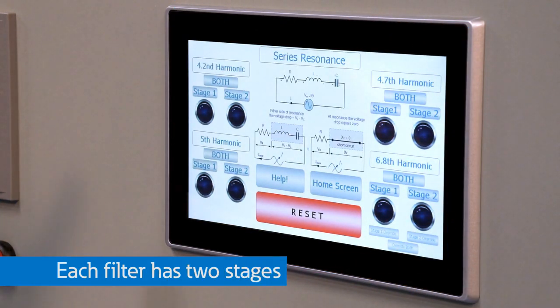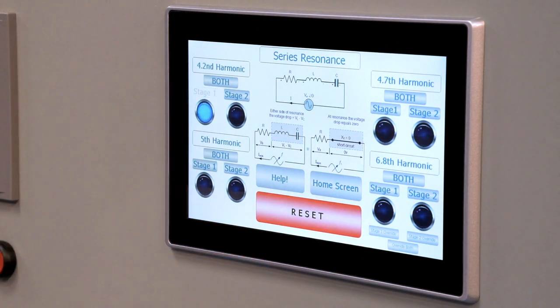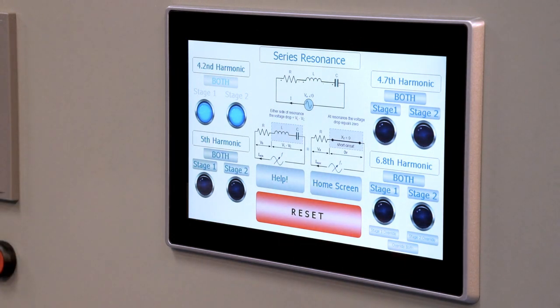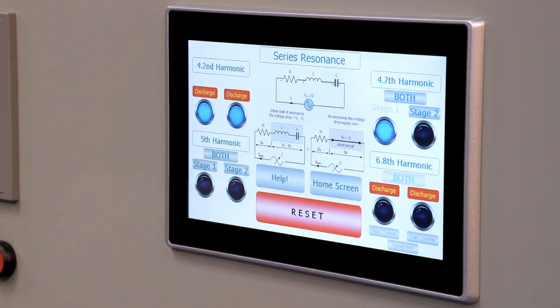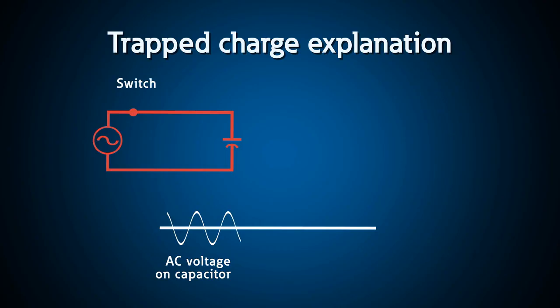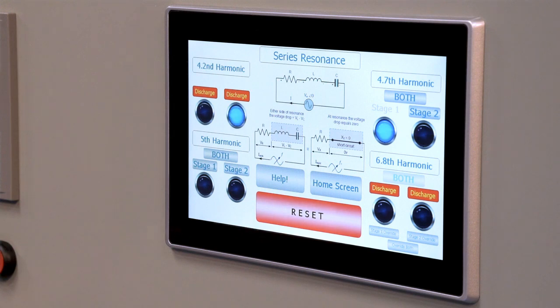Each filter has two stages. For example, if we wanted to turn on the 4.2nd harmonic to do power factor correction, I could turn on stage 1. If I need more power factor correction capacity, I can hit the button for both stages. Upon switching from the 4.2nd harmonic to the 4.7th or the 5th in order to do harmonic filtering, we're going to notice that stage 1 and 2 of the 4.2nd are going to have a cooldown timer. This allows the elimination of any DC trap charge on the capacitors. The capacitors could be charged to the negative voltage peak of the system, and if you switch them back in too fast, the system could be at the positive voltage peak. For a 480-volt line-to-line RMS system, this could be upwards of a 1,400-volt potential difference, damaging the capacitors.